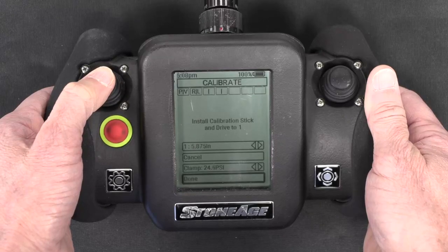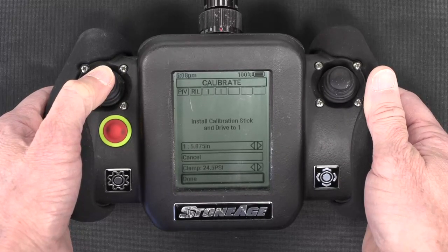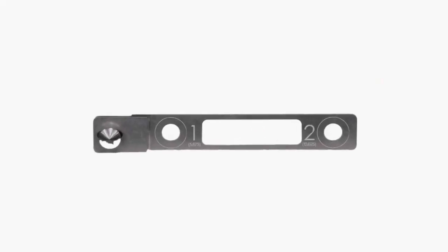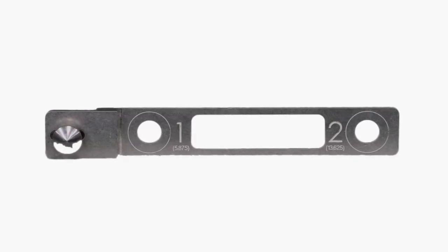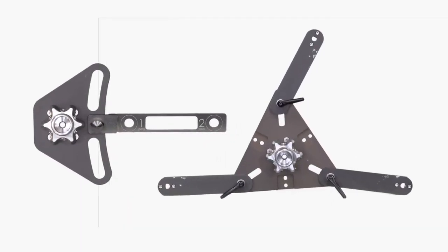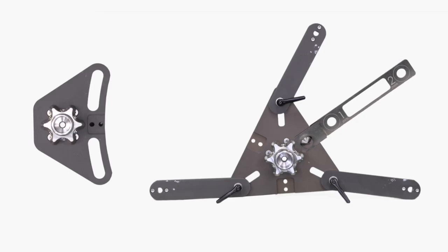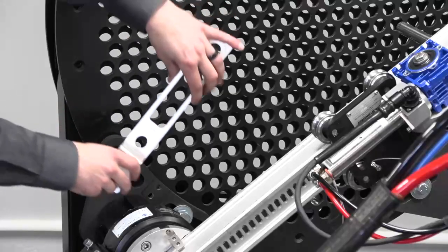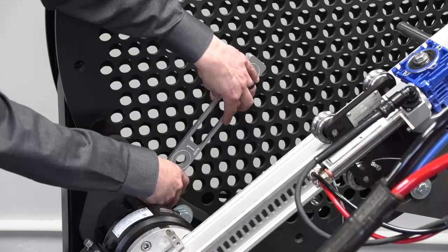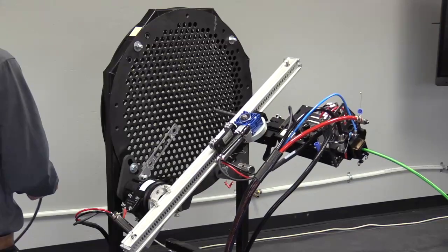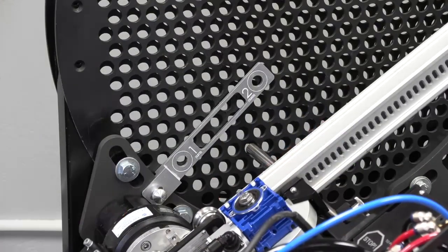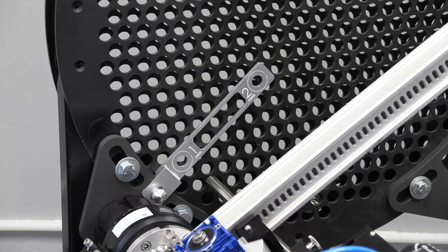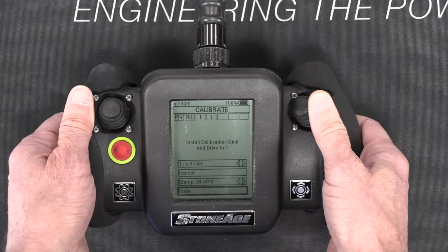The display will instruct you to install the calibration stick and drive to position 1. The calibration stick included with the system will connect to the standard mount, or the spider plate mount included with the confined space kit. Attach the calibration stick to the mount you are using. Then drive the tractor so that the guide tube lines up with the hole labeled 1. Use the right joystick to drive the tractor in any direction.